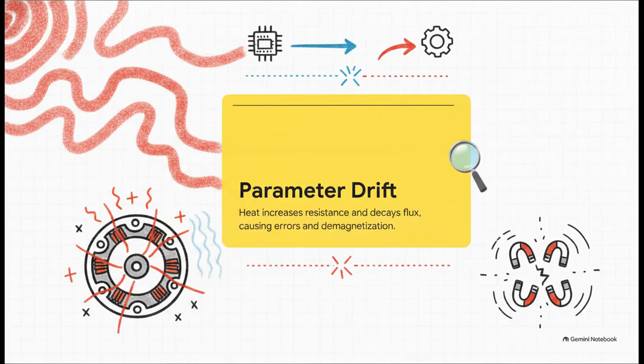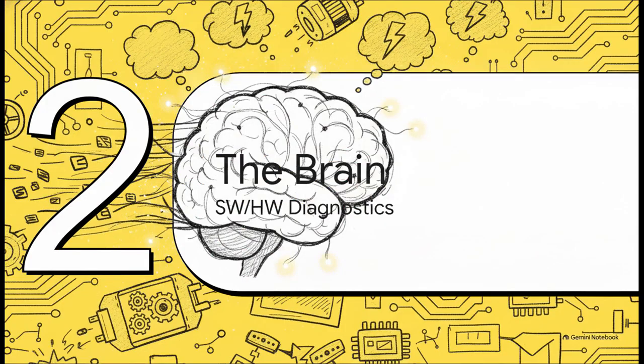Now, this is where it gets really interesting. Heat creates this hidden killer where the physical properties change so much that the software essentially loses track of reality. Engineers call this parameter drift or model mismatch. Extreme heat can increase the stator's copper resistance by 30 to 40%. It can even double it in some cases. At the exact same time, the permanent magnets suffer thermal decay. This creates massive calculation errors. The software thinks the motor is in one state, but the physical hardware is doing something completely different. That leads to control vector misalignment and, potentially, the permanent demagnetization of the motor. It's basically flying blind. Moving right along to Section 2, the brain, looking at software and hardware diagnostics.